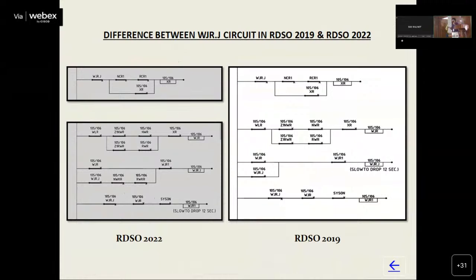In 2019 logic, there was a fixed window of 12 seconds as output from the EI system. One 12-second window will be there as output from the system, but there was no provision that once the point is set to normal, the supply should be cut. In the logic itself, there was no provision that once the point is set, this bit, the output of the WJR bit, should be cut. This provision was not there earlier.